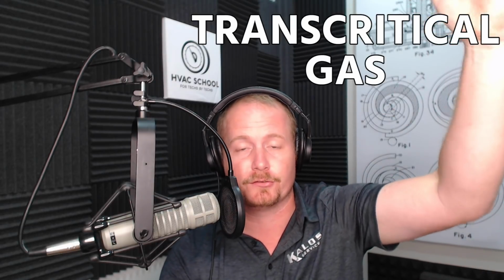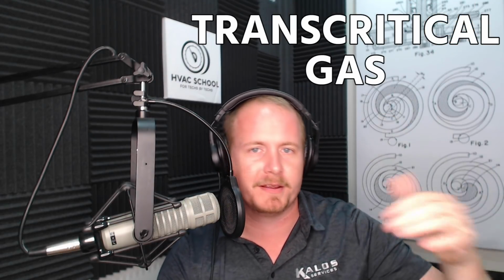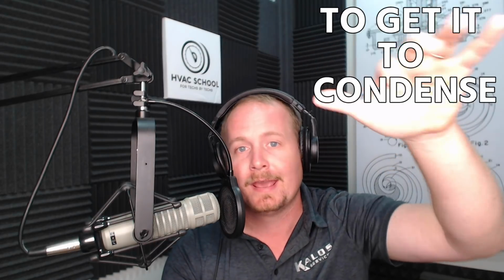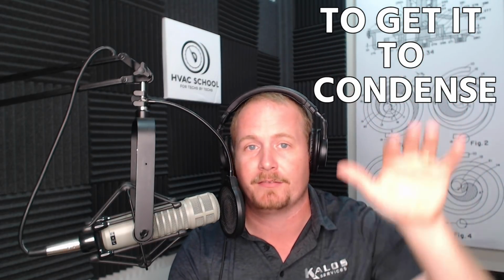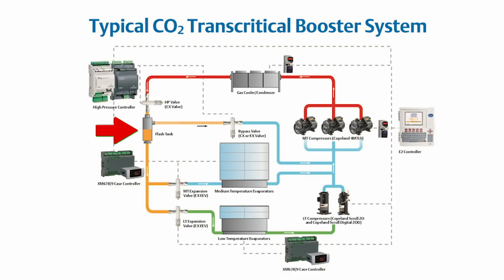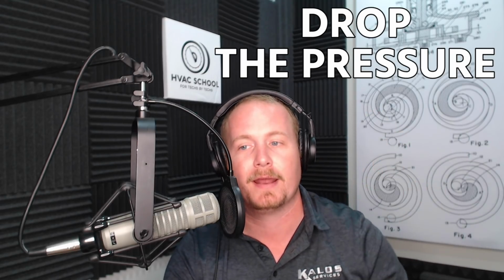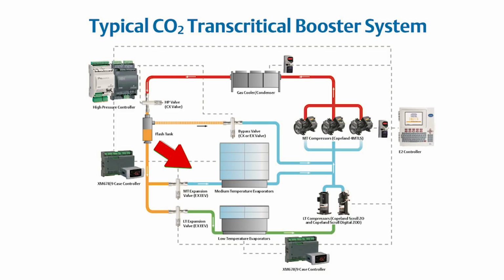In this case, we have transcritical gas. It's not, I can't really say vapor, because it's not vapor. But you have this transcritical gas, and in order to get it to condense, we have to drop the pressure. And so we do that in that flash tank.